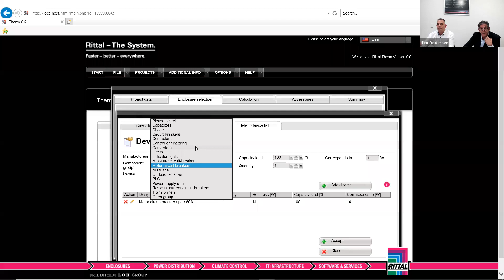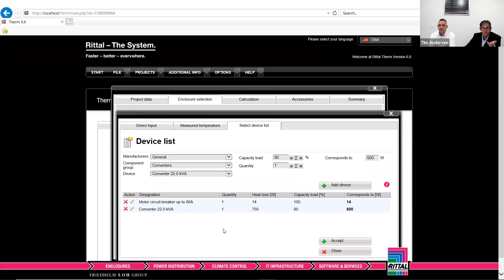Because I'm using a fan and filter setup, I'm going to pick something around 22 kilowatts, 22 kVA. Now, if you throw power factor at that, of course, you'll get your kilowatts, and you'll see a capacity load of 100%. Most drives don't work all the time at 100%. So we would change that figure to 80% as an example. We'll just do that once, and then we're going to add this device, okay? So this device here has become our most significant heat load, right? Now we're going to accept all this, and we're going to provide a calculation.